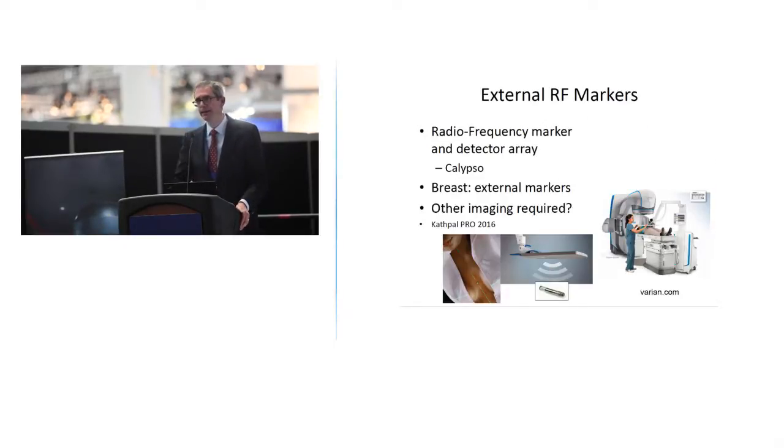The last technique that I'll mention is the Calypso system or external RF markers. These are placed as I understand it every day on the patient, so there might be some variation of how they're placed on the patient surface. Again you can look at the relative motion but perhaps need some other technology to position the patient relative to isocenter. But it's a nice application of this technology.